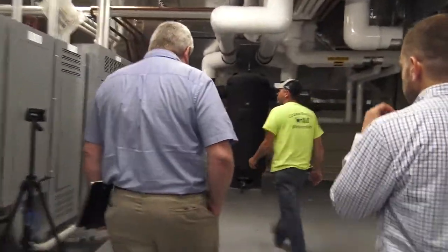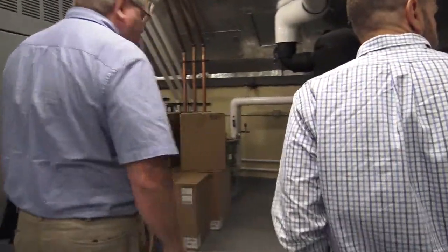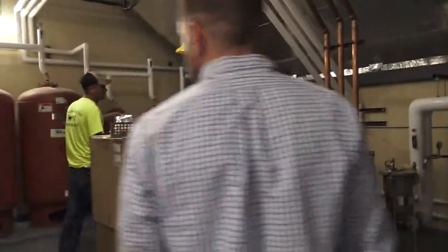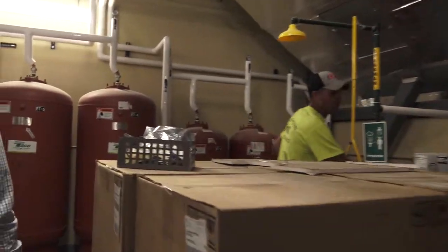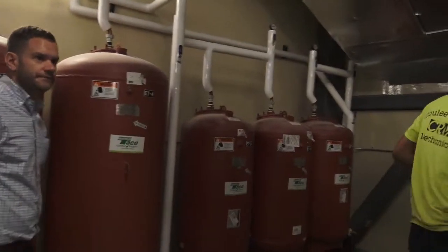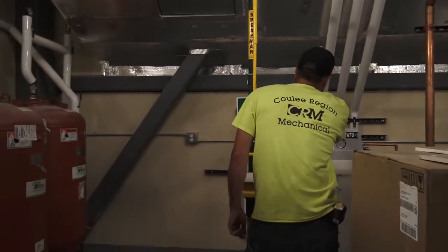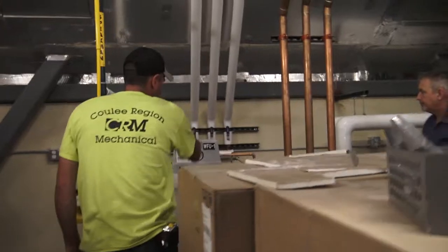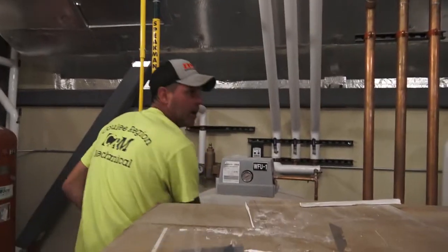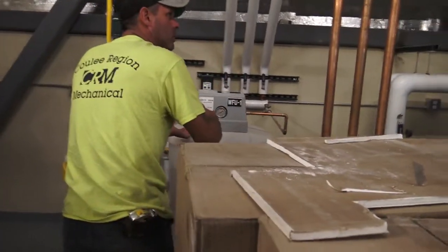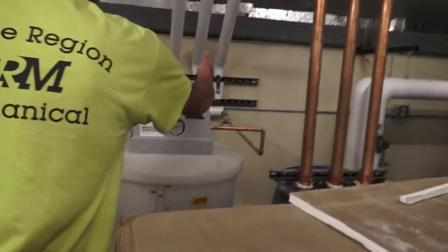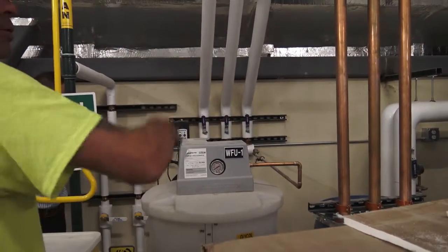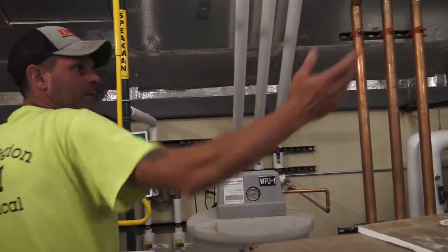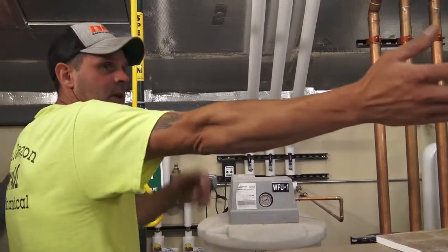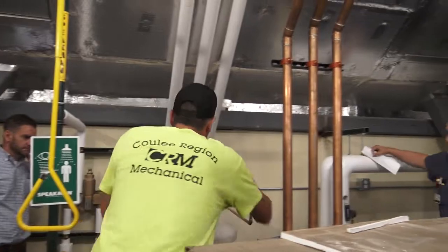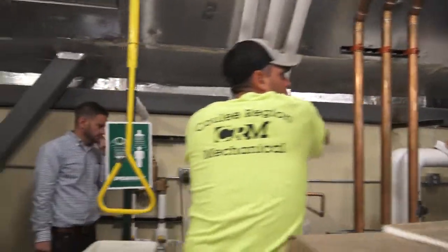Is this already preset, or what is it? I think it's set at 12 pounds right now. So if it gets below 12 pounds, this little pump will kick on automatically. That's your alarms and everything for this, so when you get below whatever you've got set, it'll send off an alarm and you've got to add more glycol. But this is all set, it'll just do what it's got to do. If you lose glycol, it'll keep pumping. But if you need to add, or say you drain down a pump or something, just come over here, undo that, pour it right in, and reclaim it.